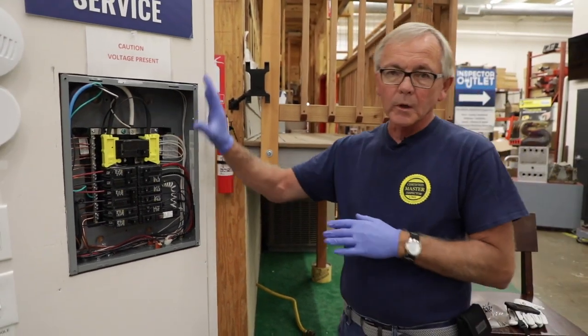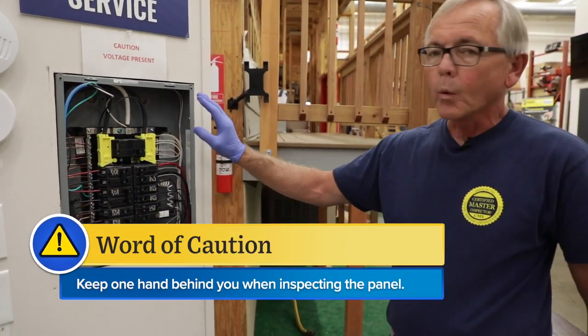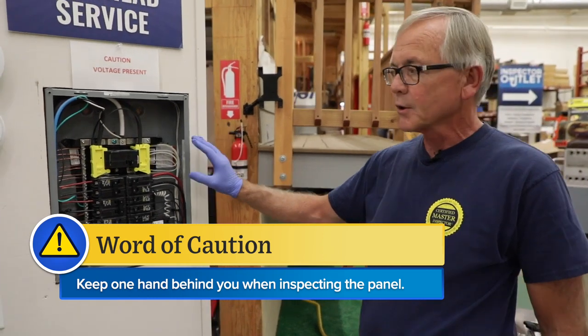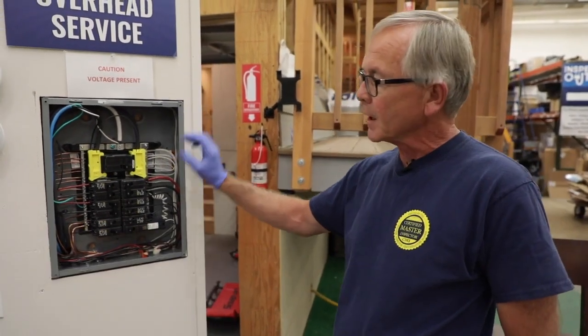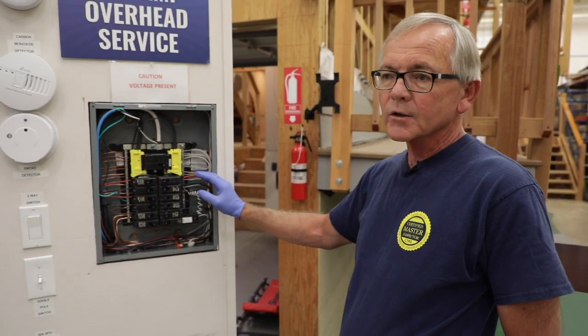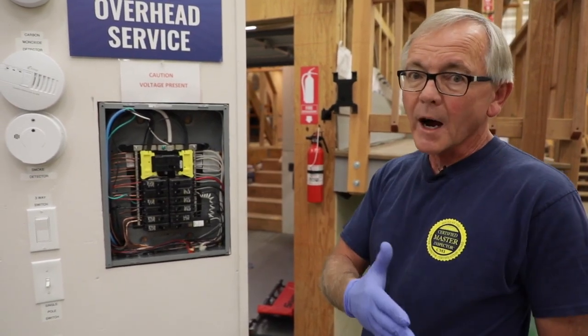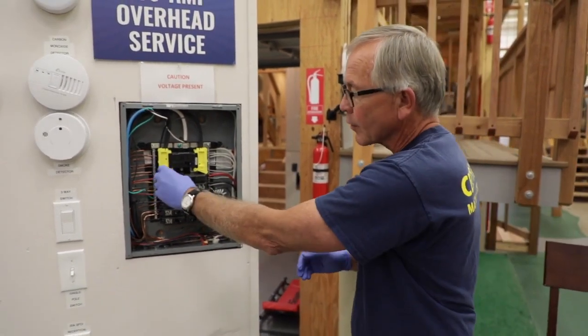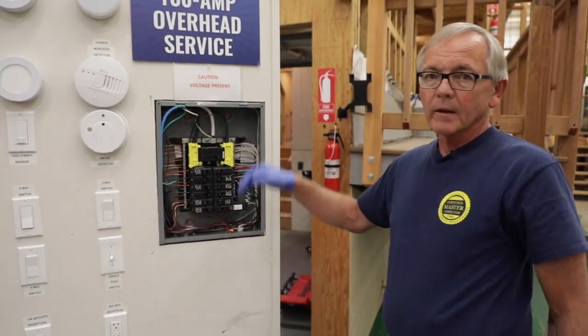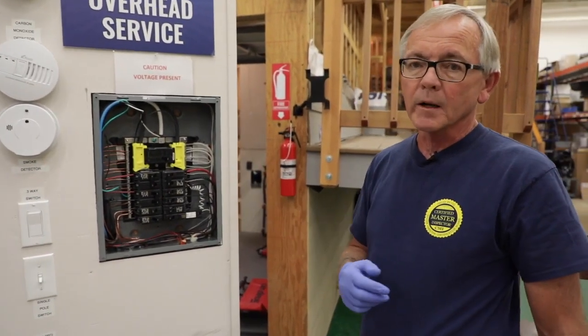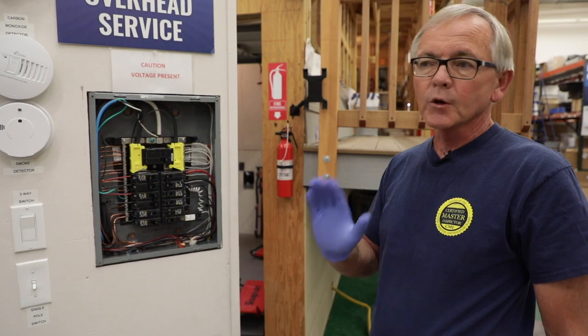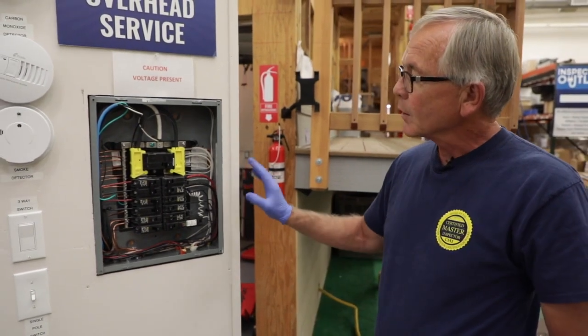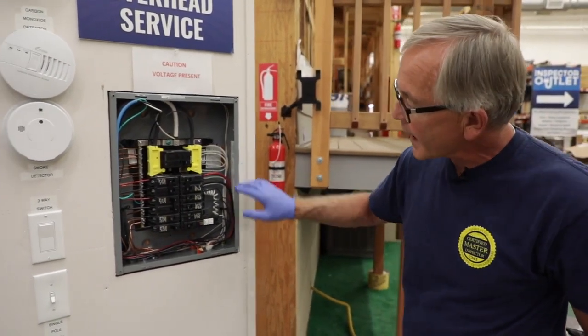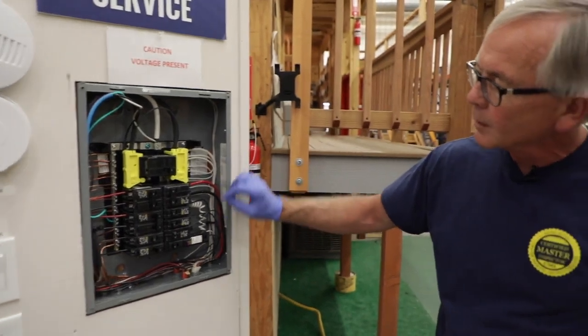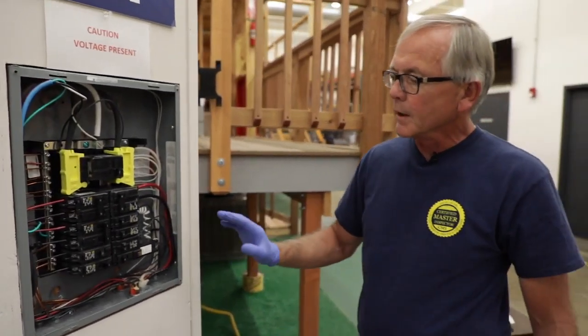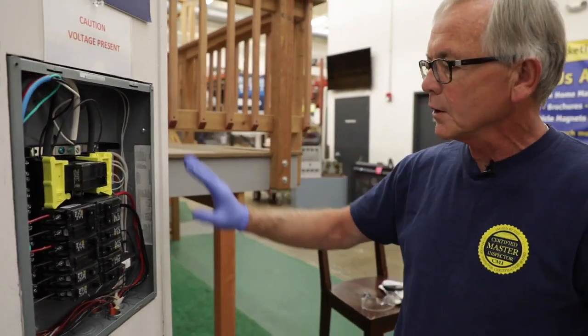Always, when you're in and around the panel, keep one hand behind you, because electricity flows, again, from the hot energized wires through your body. If I had my hand on a ground wire or a neutral, that circuit would run through my body. I want to restrict that totally. So what I want to do is just use one hand. If I have to, I can use my little dowel, move some wires around. But now I'm going to just do a typical visual inspection.